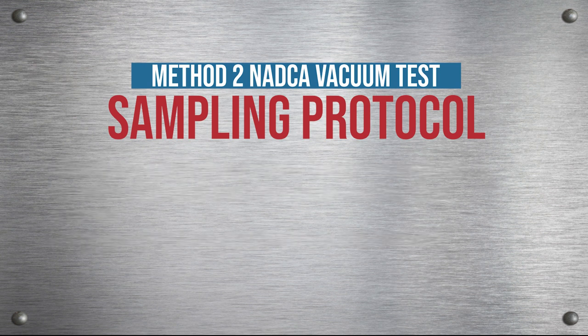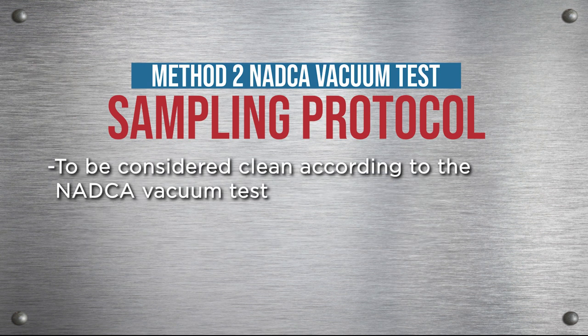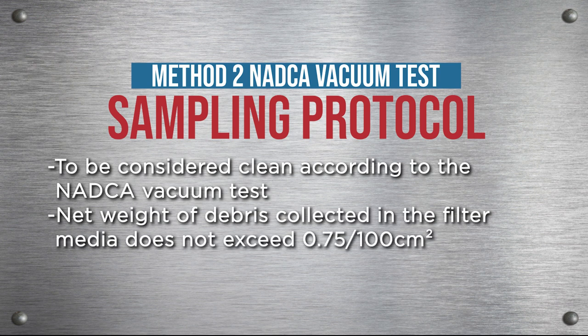To be considered clean according to the NADCA vacuum test, the net weight of the debris collected on the filter medium does not exceed 0.75 milligrams per 100 centimeters squared.